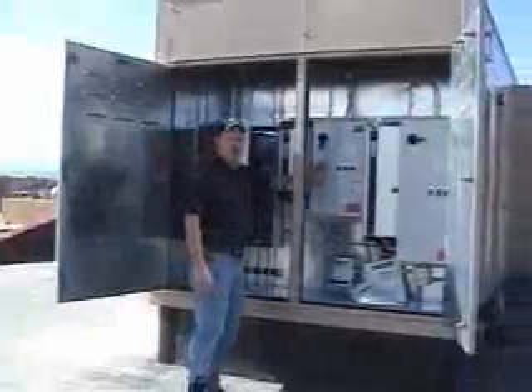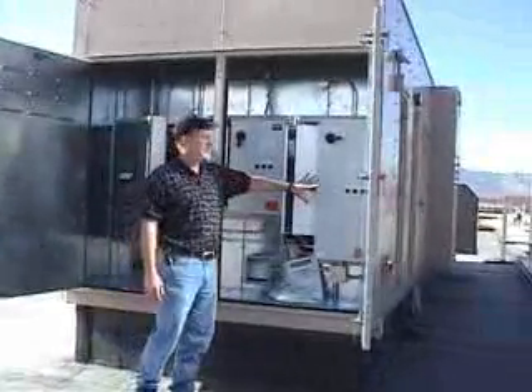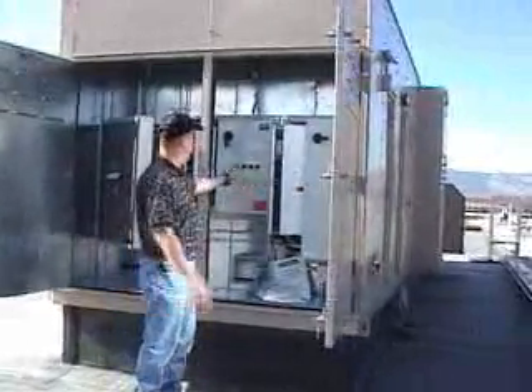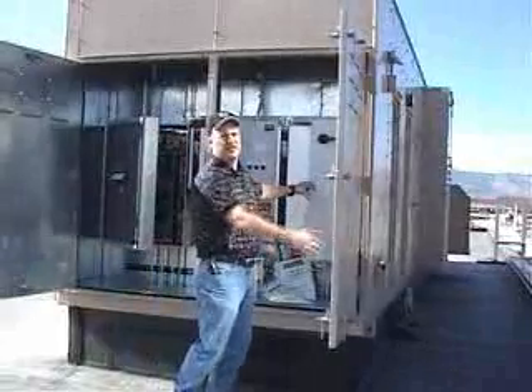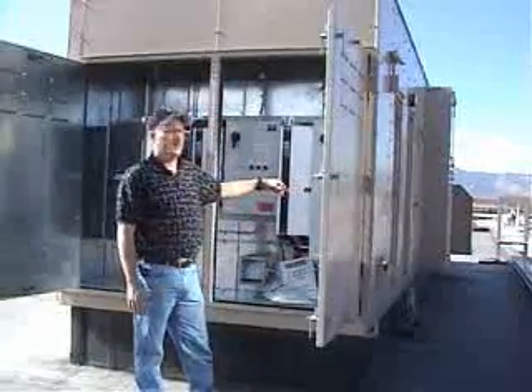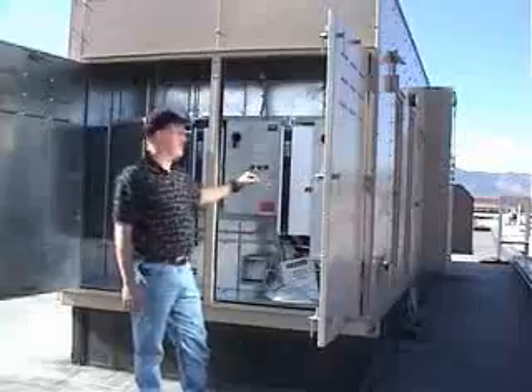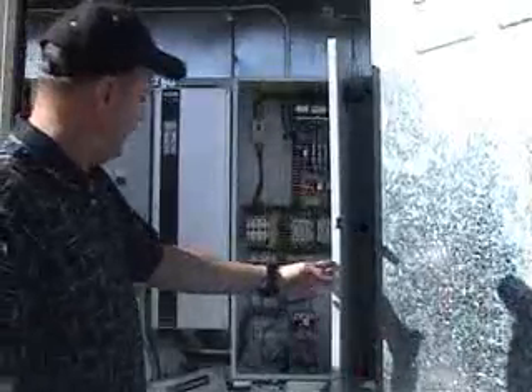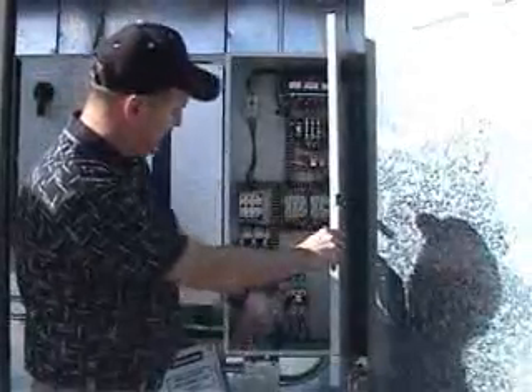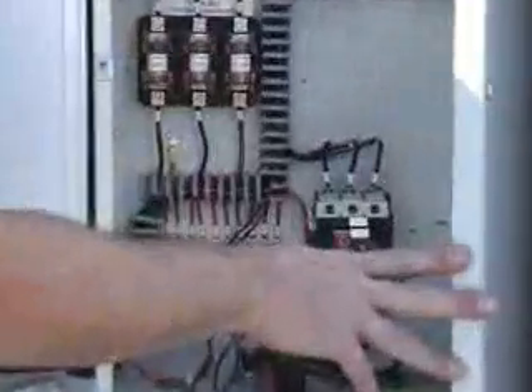So these devices here are what we call the variable frequency drives. We have one for the supply fan and one for the return fan. You'll notice the supply fan is larger because it has a larger amperage motor. This side is really just the nuts and bolts. These are our contactors. This is our thermal protection down here for the motor, so we don't overheat and burn up our motor. We have some big transformers up in here. Most of the things in here you don't want to touch; it will ruin your day.